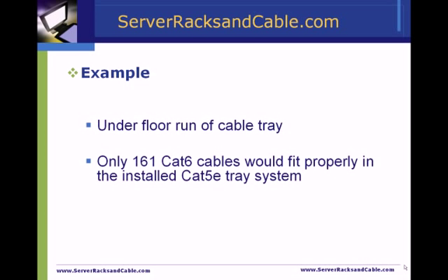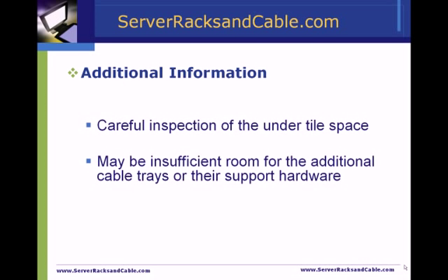This can cause difficult or unsolvable problems to find the underfloor usable space to add additional cable tray and supports. These changes have to be solved before starting to install a new computer room cabling setup. Careful inspection of the under tile space available for installation of additional cable tray and supports has to be done during the planning phase of the job to ensure it is possible.